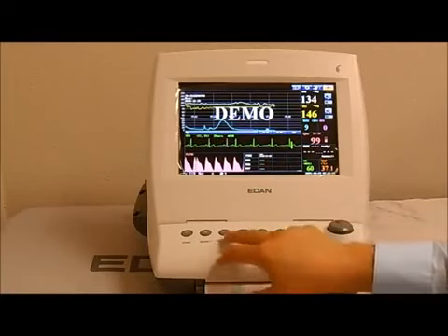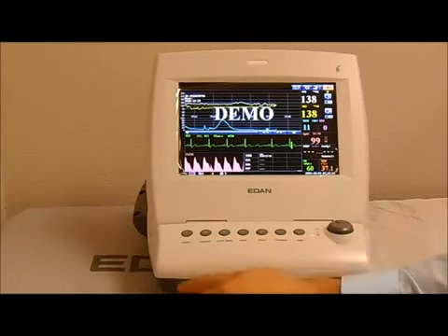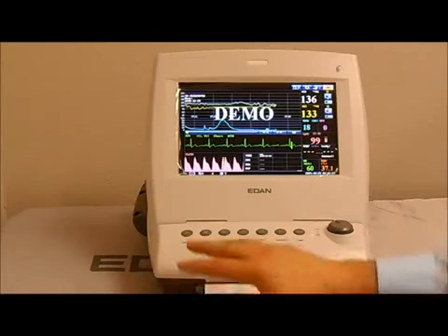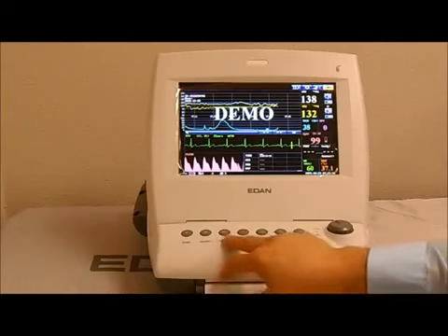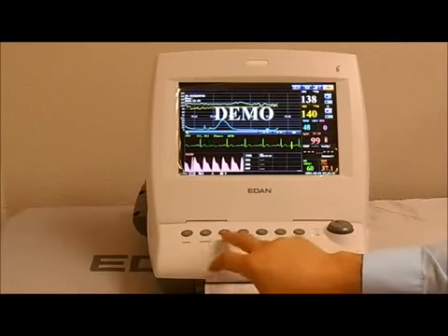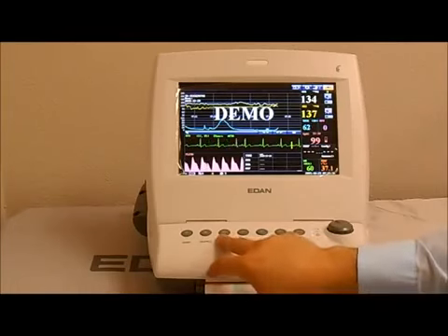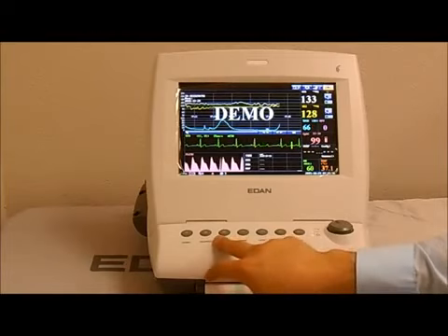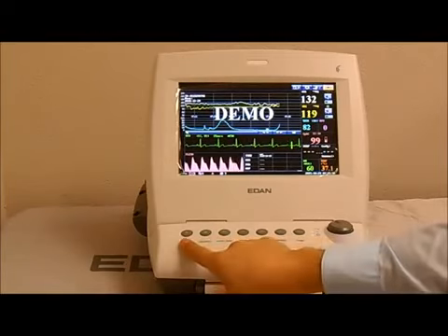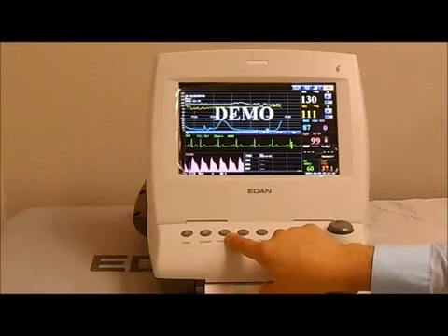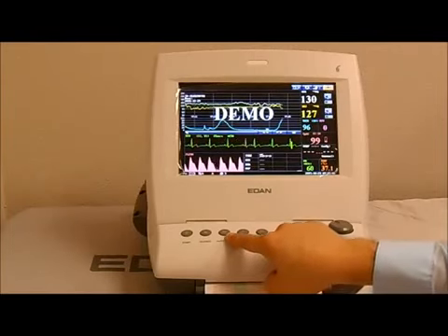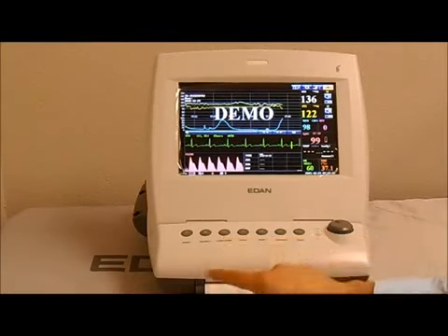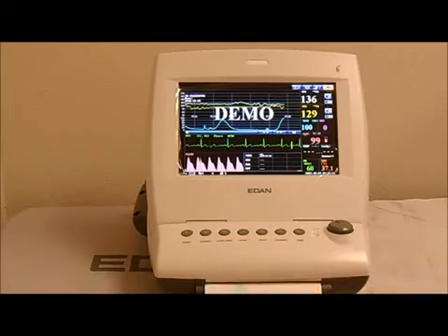The auto zero also occurs when you press the start key. So when you press start, it starts a new session and automatically sets the auto zero. You don't have to press the auto zero key every single time you have a new patient. It's automatically performed when you press the start key. Rather, it's there in case the patient moves and the transducer falls off, so that you don't have to start from scratch, from the very beginning. You only press the auto zero.